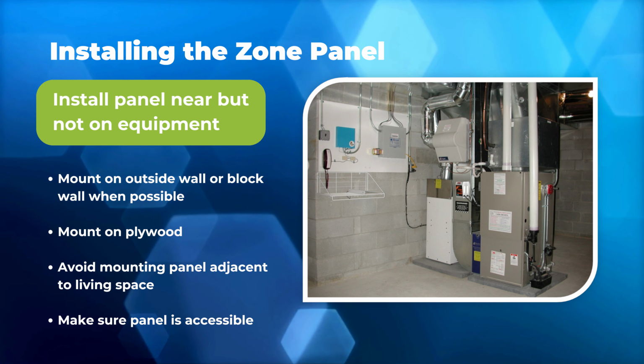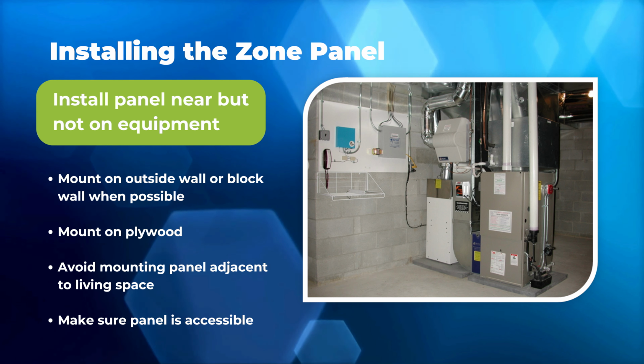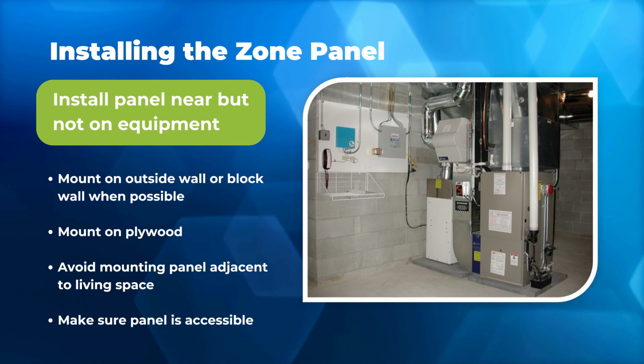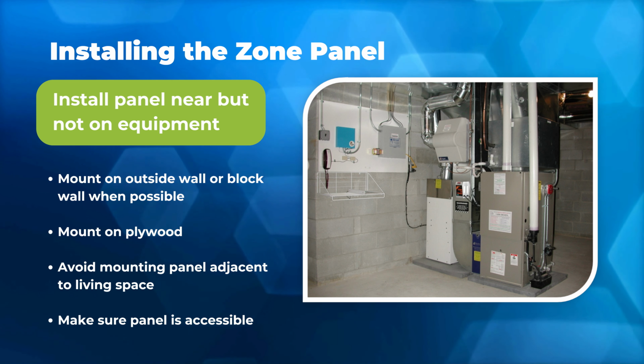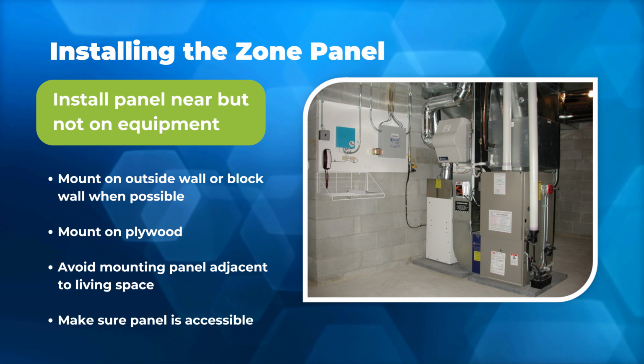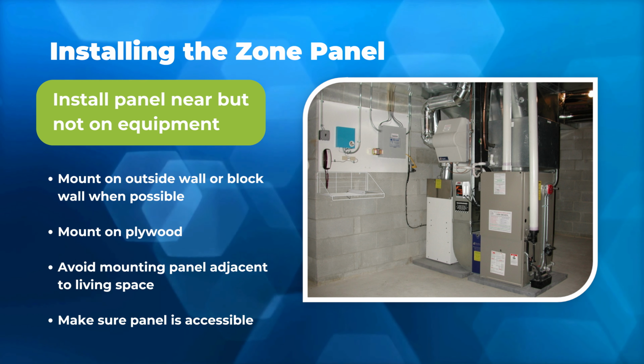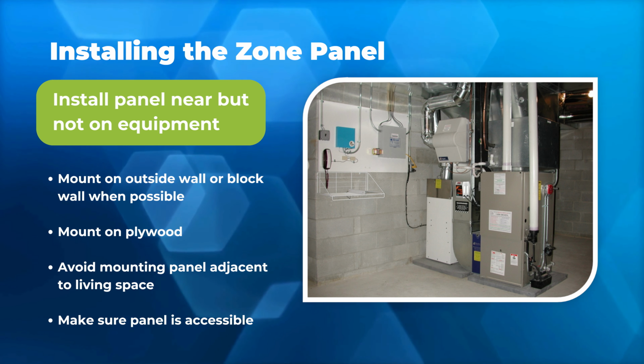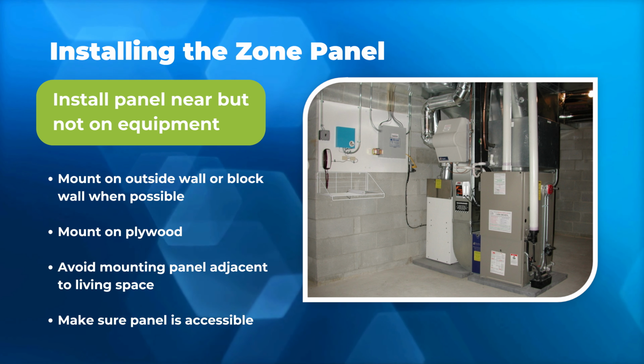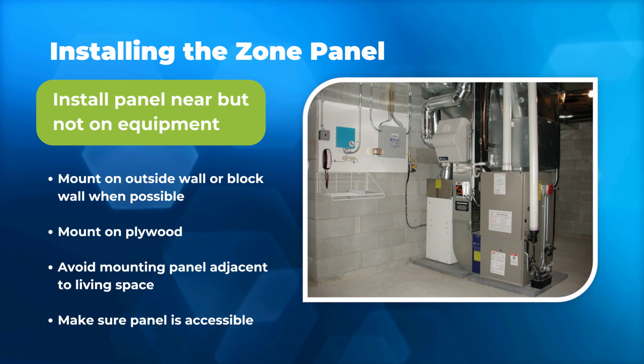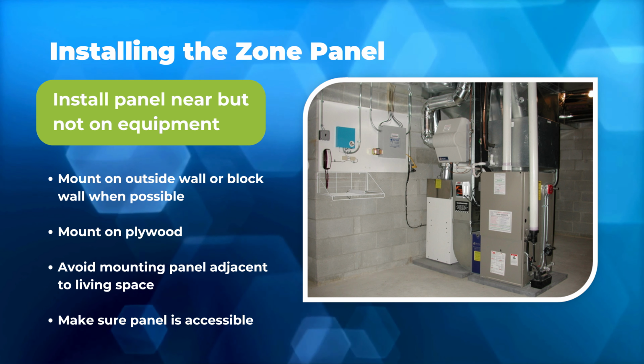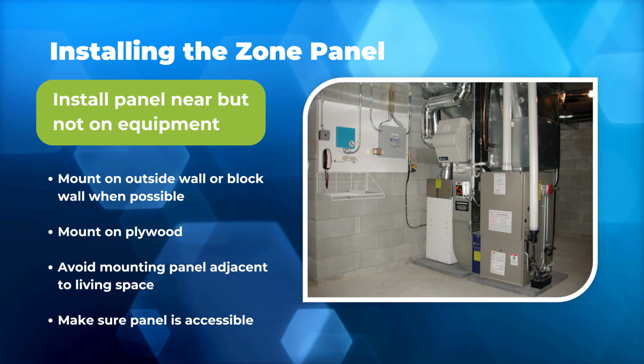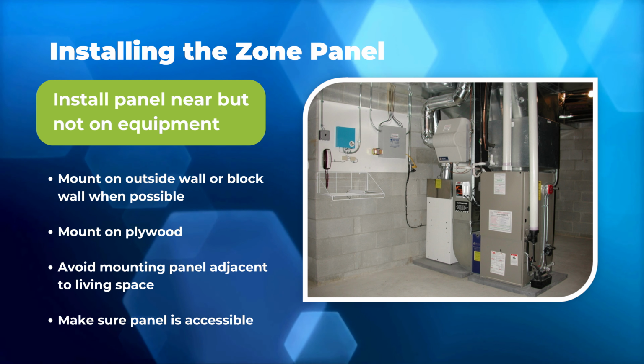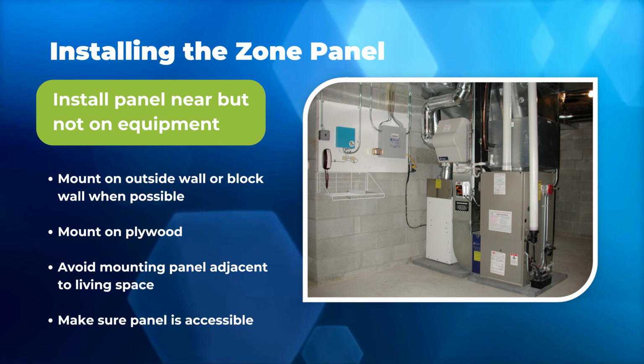When looking for a pristine mounting position, the best thing you can do, if you're in a basement, is to mount it to a block wall. When you're doing that, you're going to want to put it on a piece of 3/4 inch plywood that's kind of going to absorb the sound a little bit so you don't have it just echoing on the cinder block itself. If you don't have access to a cinder block wall or something like that and you have to do it on a drywalled wall, you're still going to want to put it on the 3/4 inch piece of plywood.